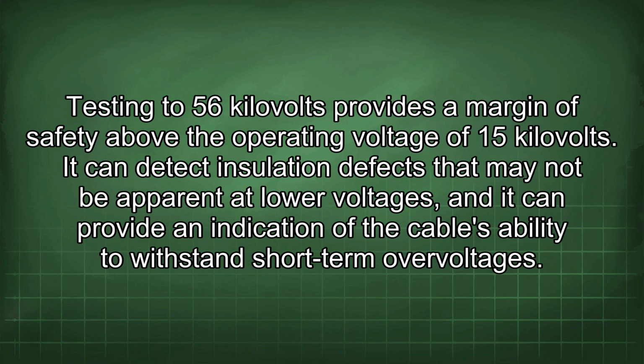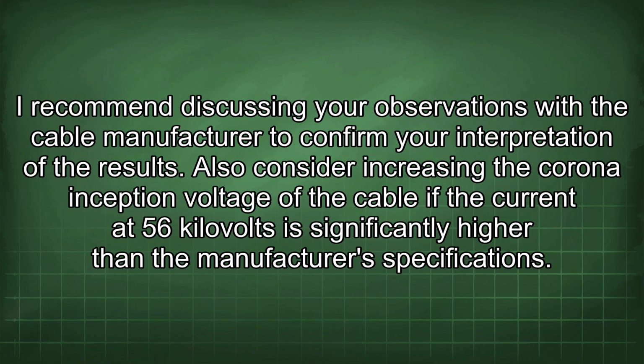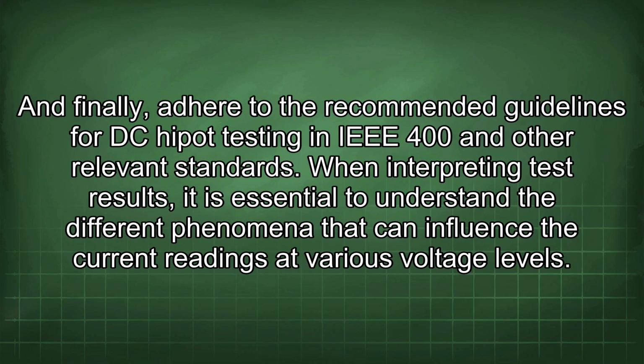Testing to 56 kilovolts provides a margin of safety above the operating voltage of 15 kilovolts. It can detect insulation defects that may not be apparent at lower voltages, and it can provide an indication of the cable's ability to withstand short-term overvoltages. I recommend discussing your observations with the cable manufacturer to confirm your interpretation of the results. Also consider increasing the corona inception voltage of the cable if the current at 56 kilovolts is significantly higher than the manufacturer's specifications. And finally, adhere to the recommended guidelines for DC hipot testing in IEEE 400 and other relevant standards.